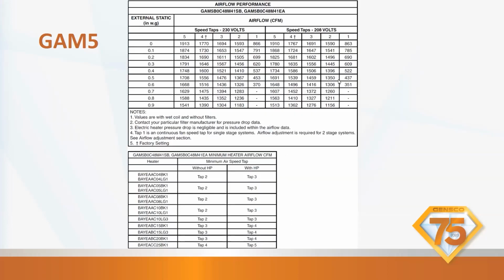Again, here's a GAM5B, which is a variable speed, and it's going to show us the speed taps. Actually, I lied. This is a torque motor. It's going to show us the speed taps according to external static pressure and the volume of air going through it.